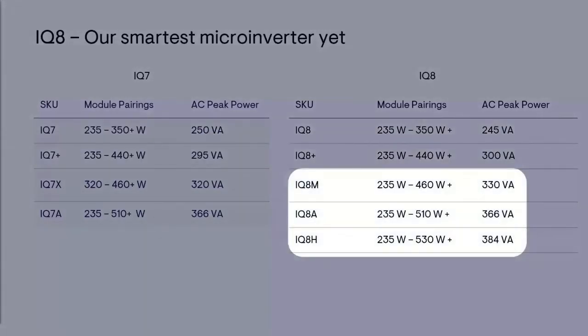We then have the IQ8M, a new power class, and the IQ8A and IQ8H with progressively higher power ratings. The IQ8H is our most powerful model, rated at 384 VA, and can be paired with solar modules up to around 530 watts in most climates with little to no losses to inverter saturation.